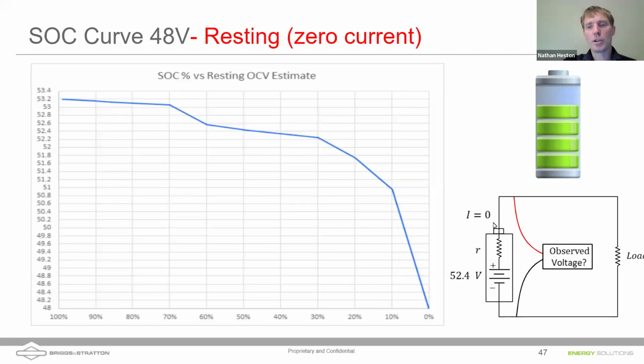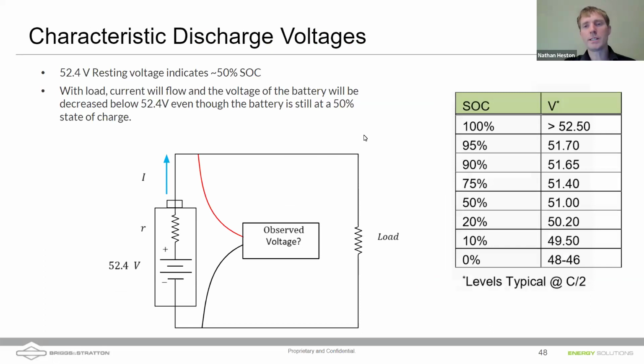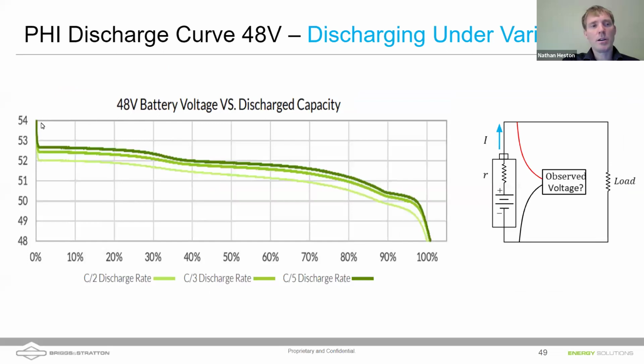Now, this is resting, meaning the current going into or out of the battery is zero. If I'm discharging at faster rates—remember those state of charge to voltage values I just gave you—when discharging, we lose some voltage across the internal resistance, so the displayed voltage on the inverter during discharge will be below the resting voltage. I point this out because here I don't have the resting curve shown on top, but it would sit higher up.